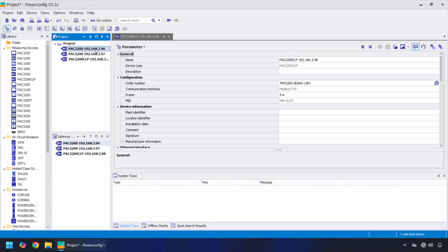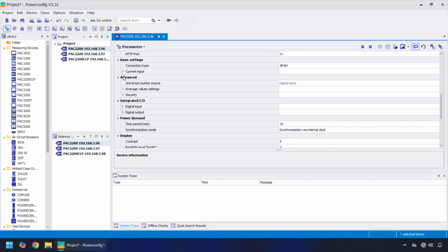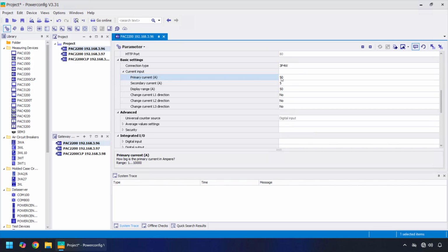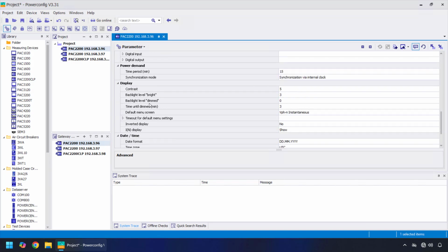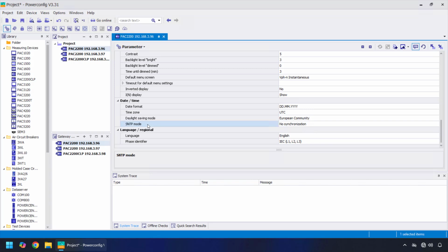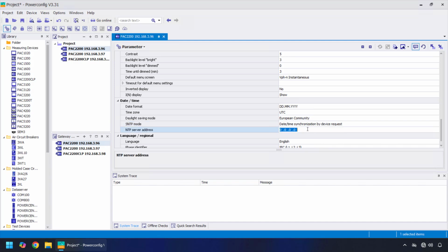Then let's have a look at the basic settings of the PAC meters. Minimum configuration for all of them would be to set the correct ratio for current transformers. The primary current in my application will be 100 amps and secondary 5 amps. The second important thing is the time synchronization. We have to define an SNTP mode, let's say synchronization by device request, and set here the address of the NTP server. If you have your own NTP server, you can take this server, or in combination with Powercenter 3000, set the IP address of Powercenter 3000 here.